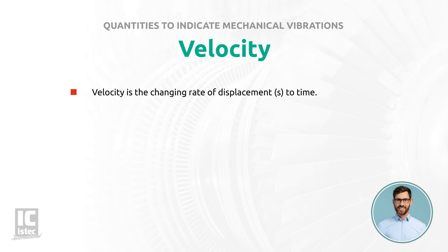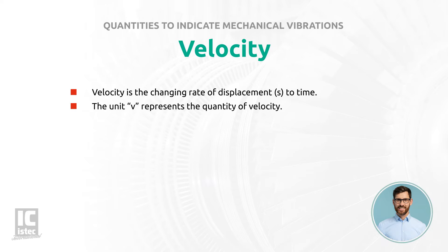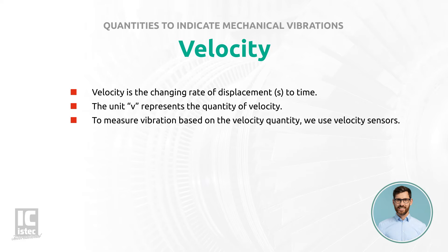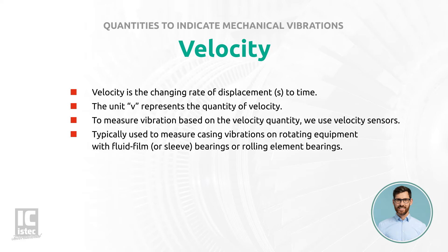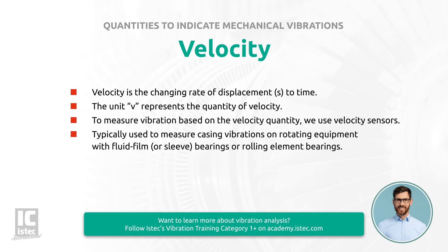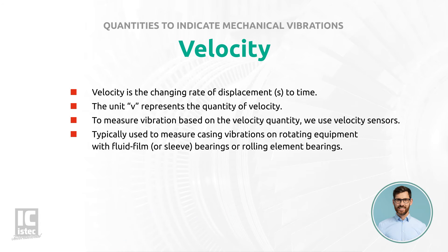Velocity is the changing rate of displacement to time. The unit V represents the quantity of velocity. To measure vibration based on the velocity quantity, we use velocity sensors. These sensors are typically used to measure casing vibrations on rotating equipment with fluid film, sleeve bearings, or rolling element bearings.